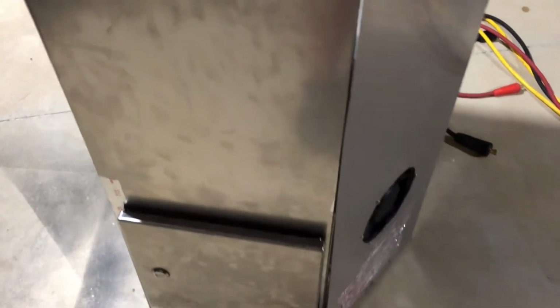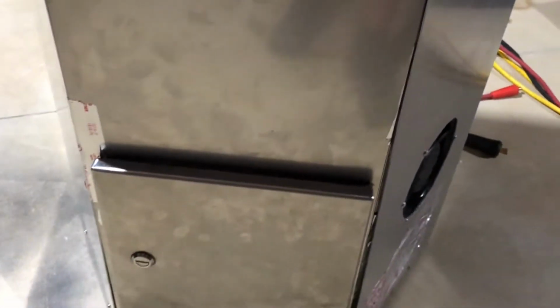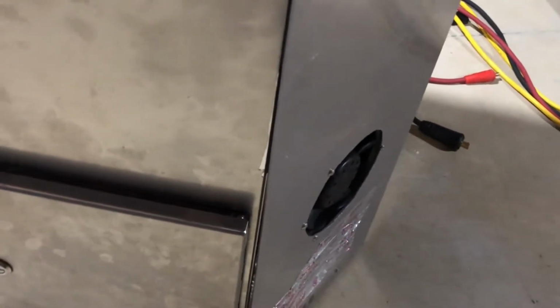So how this lamp house actually works is the reason that it's sealed is this bottom section is airtight, or as good as I could get it to be airtight. You can see underneath the reflector, all around, there is duct tape to prevent any air leakage. So when this bottom half is pressurized, and you'll see it better in a couple seconds, the air escapes through this hole.